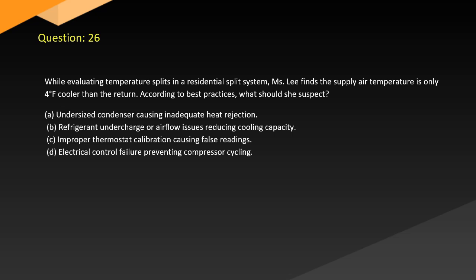Question 26. While evaluating temperature splits in a residential split system, Lee finds the supply air temperature is only 4 degrees cooler than the return. According to best practices, what should she suspect? A. Undersized condenser causing inadequate heat rejection. B. Refrigerant undercharge or airflow issues reducing cooling capacity. C. Improper thermostat calibration causing false readings. D. Electrical control failure preventing compressor cycling.